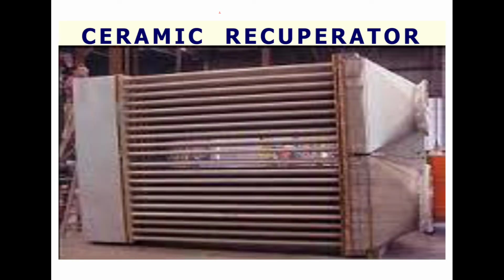The ceramic recuperator is shown. This is an industrial ceramic recuperator, where we can see small tubes, and at the end of the tubes a flat surfaced plate. Inside the plate there is an air circulation port. The tubes convey the gases, so the circulating air removes the gas heat energy in order to maintain the gas temperature.